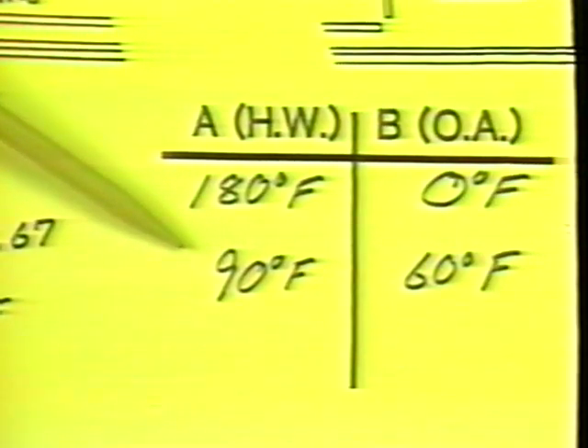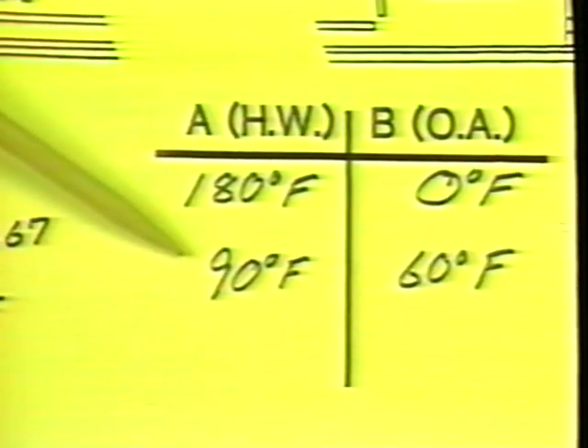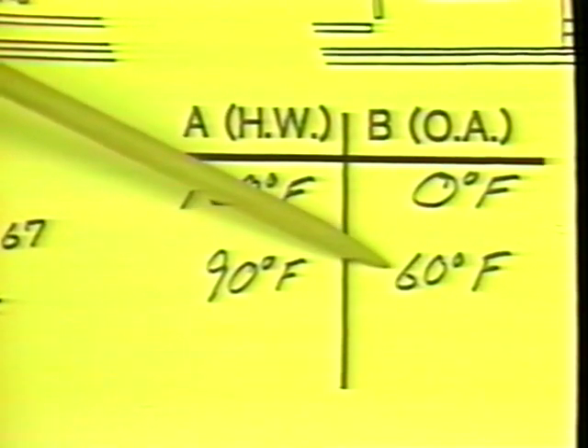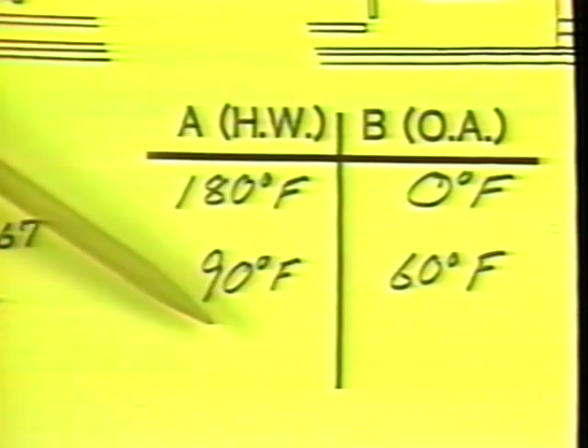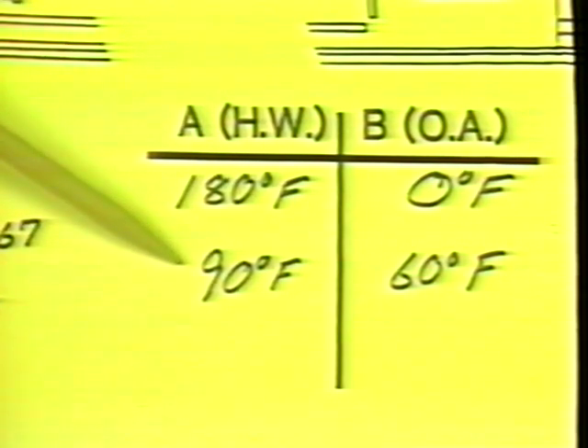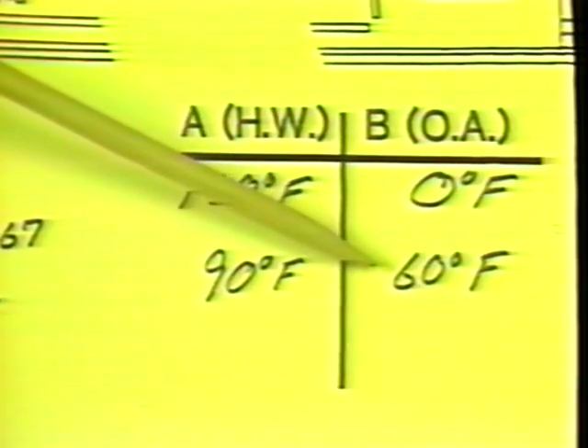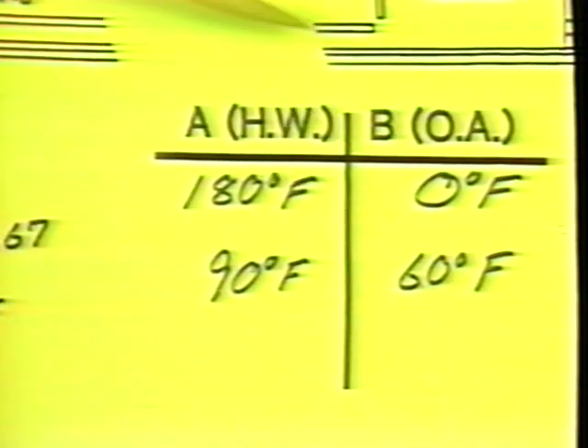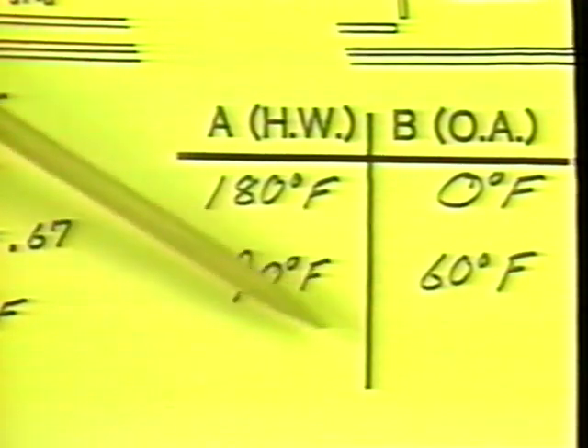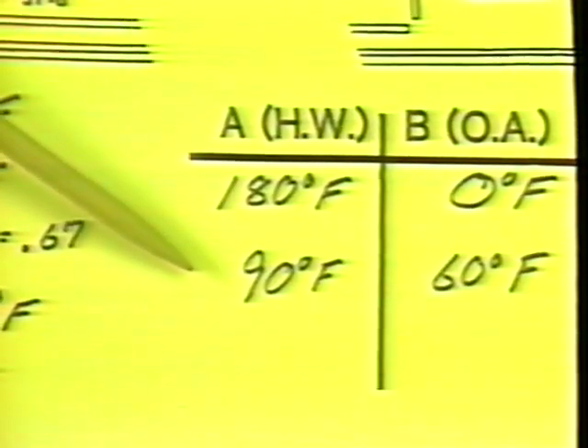The engineer will also determine a fade-out temperature, that is, some resetting variable temperature, in this case 60 degrees outside air, at which we're no longer interested in any hot water reset. In this case, we want a 90-degree hot water temperature when we reach 60 degrees outside air. Using these two sets of values, we can now determine the settings for our controller.